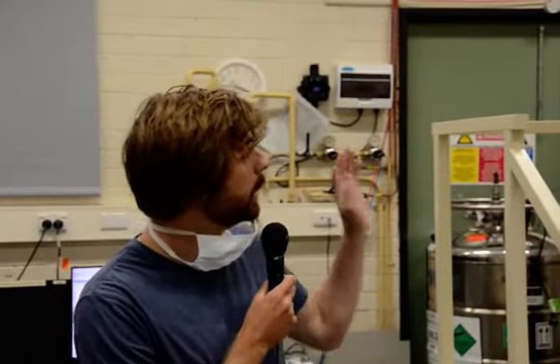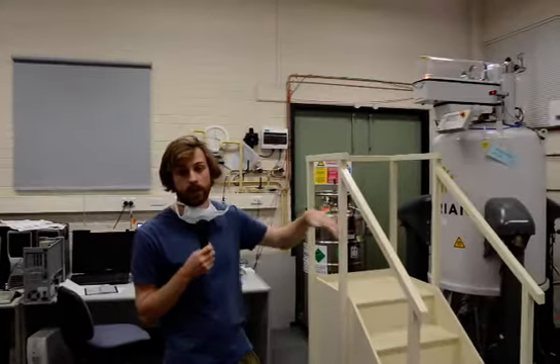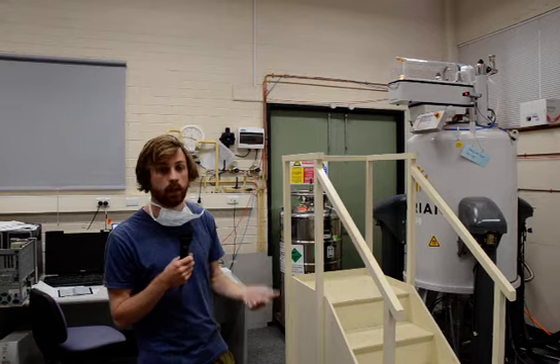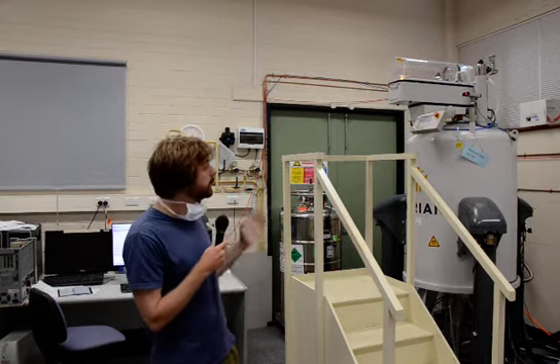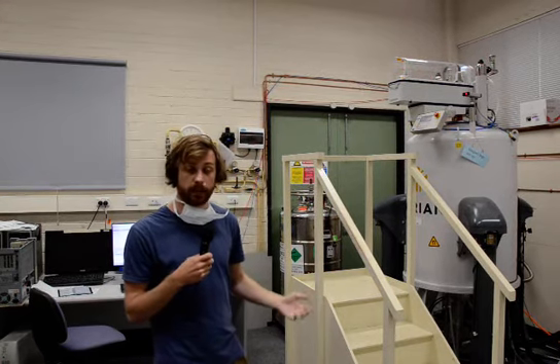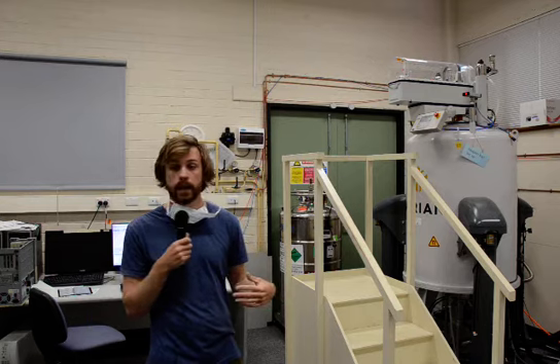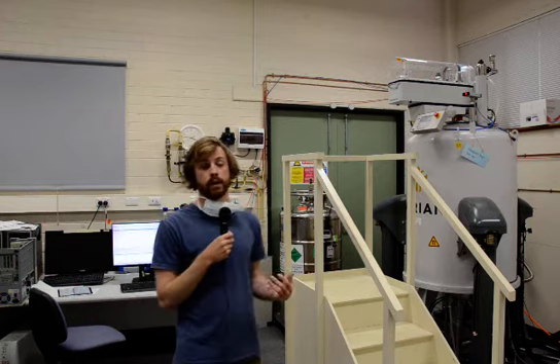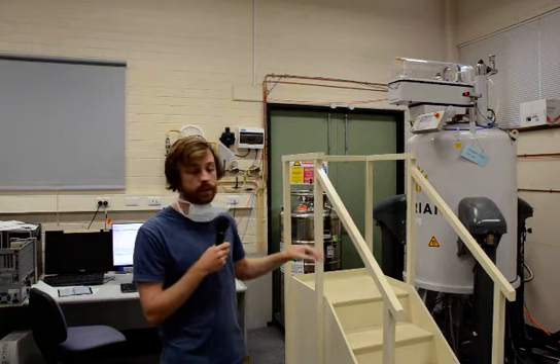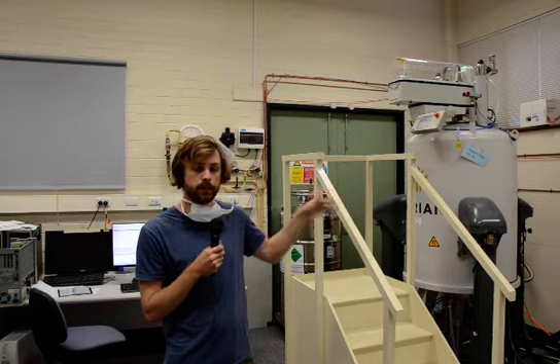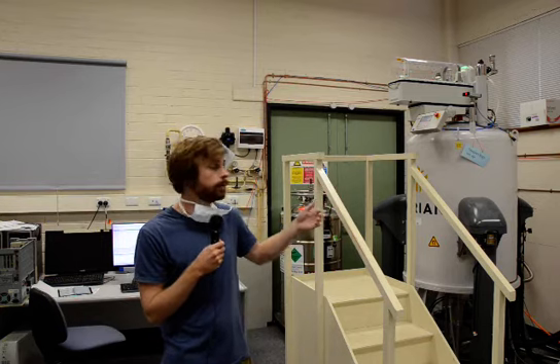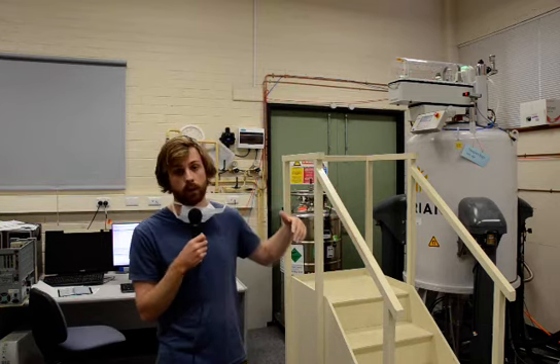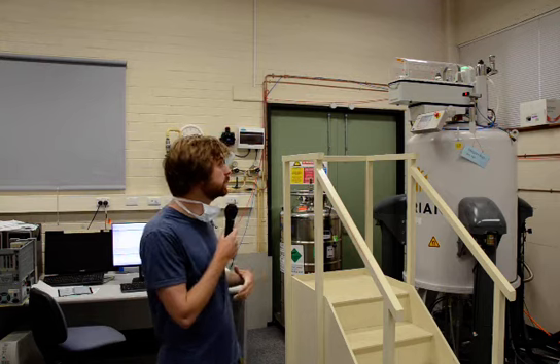This will submit the sample to the spectrometer, where it will just move the sample holders around the machine. It will automatically inject the sample for you. It will automatically run the sample by locking, shimming, and acquiring the data. And it will then automatically eject the sample as well and allow you to collect the data off the share drive. So there's really no way for you to get this wrong. If the sample ever gets stuck or anything like that, sometimes you do need to get it out, in which case the technicians at the university handle that for the users of the machine.